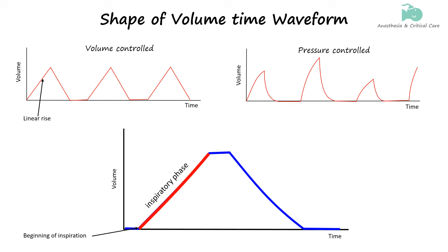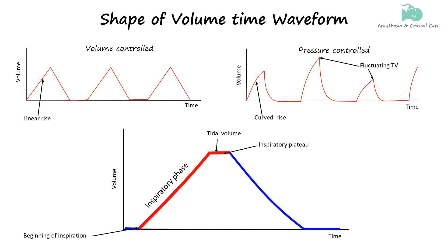In pressure-controlled modes, the rise in volume may take on a more curved or exponential shape, with fluctuating tidal volume depending on lung compliance and the pressure applied by the ventilator. The volume attained at the end of inspiration is the tidal volume. If there is a pause at the end of inspiration, known as an inspiratory hold, the waveform will display a plateau, indicating that the volume of air in the lungs is being held constant. This phase is useful for assessing plateau pressure, which provides insights into lung compliance.